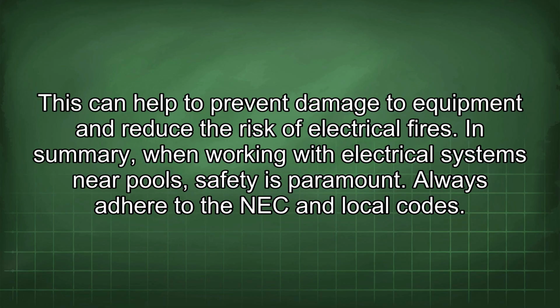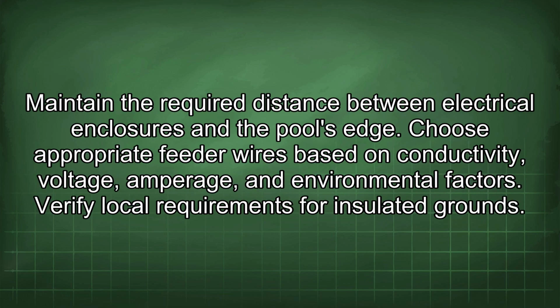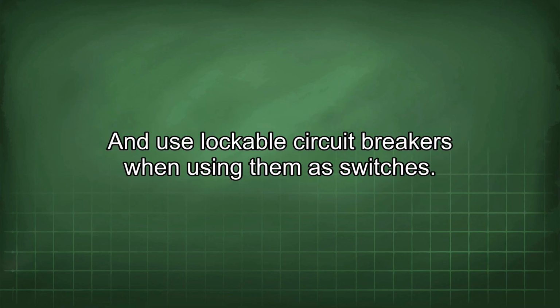In summary, when working with electrical systems near pools, safety is paramount. Always adhere to the NEC and local codes. Maintain the required distance between electrical enclosures and the pool's edge. Choose appropriate feeder wires based on conductivity, voltage, amperage, and environmental factors. Verify local requirements for insulated grounds, and use lockable circuit breakers when using them as switches.